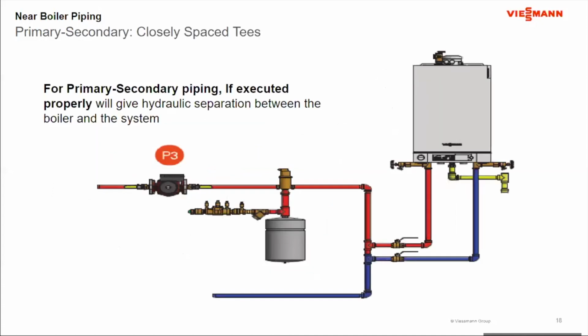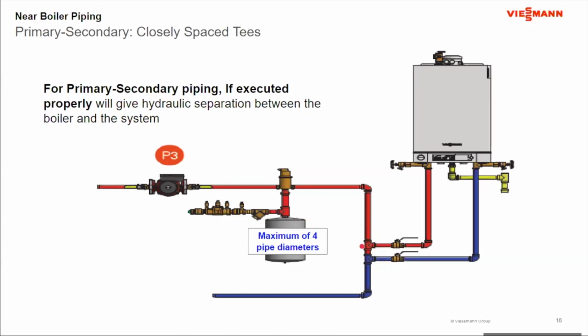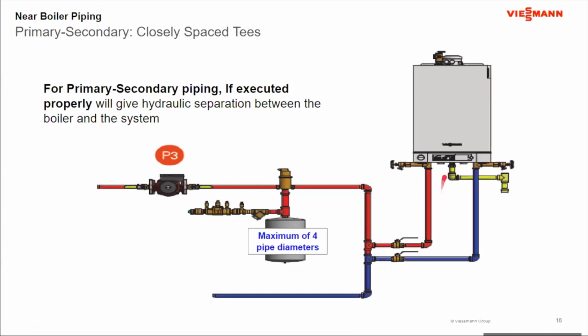Okay, now the other option is going with primary secondary. Primary secondary, I can go with either style of boilers, the wall hung water tube boiler or the floor standing fire tube boiler. Okay, so primary secondary, it's really all about this. Okay, so I'm going to have some sort of primary secondary connection. It can be closely spaced tees. The closely spaced tees should be at a maximum of 4 pipe diameters apart. I want to reduce the pressure drop in this crossover piece here. This way here, I've hydraulically isolated the boiler loop from the system loop. So the boiler loop can have a flow rate based on what's required for the boiler. The system can have a flow rate that's required for the system, and neither operation affects the other operation. So this is primary secondary as executed as closely spaced tees.